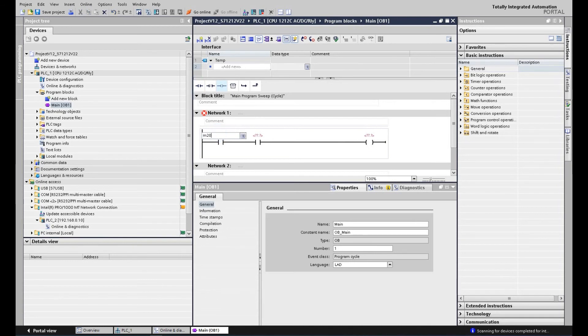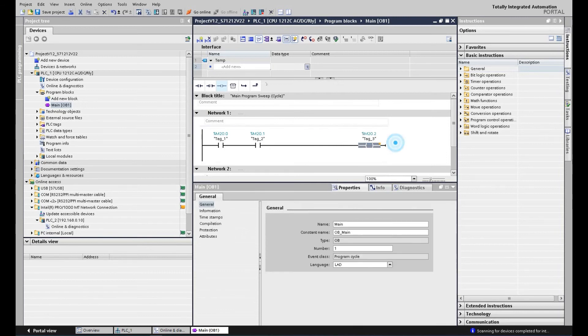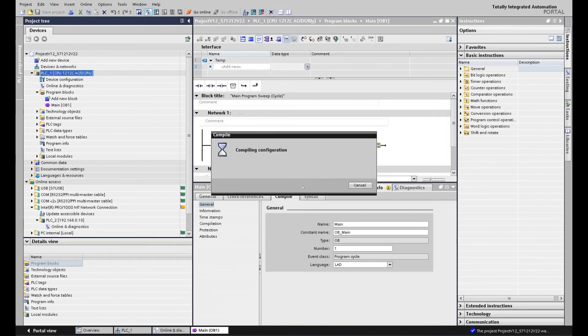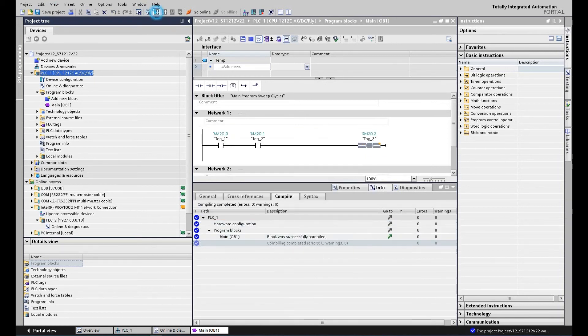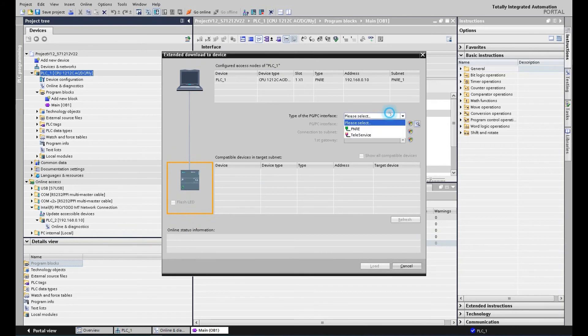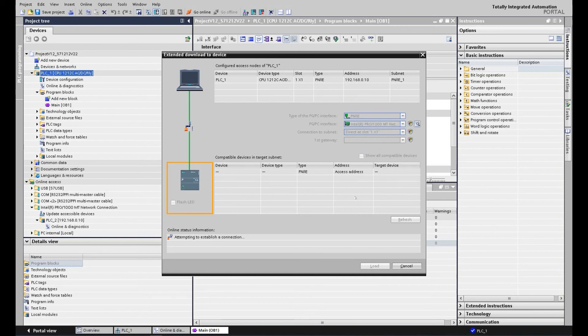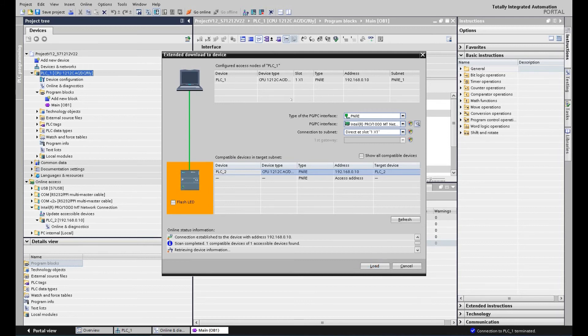The first bit M20.0, M20.1, M20.2. After finished programming, let's hit save, compile the project, and get ready to download. Select PN/IE. OK, the system already found this controller. Click the download. So our offline program will download to the controller.